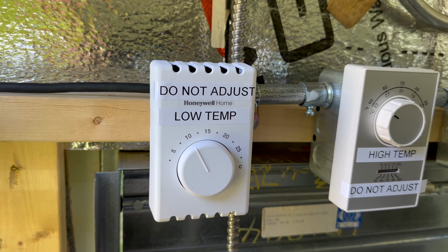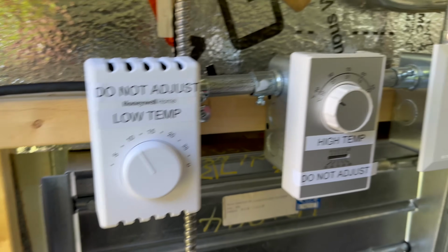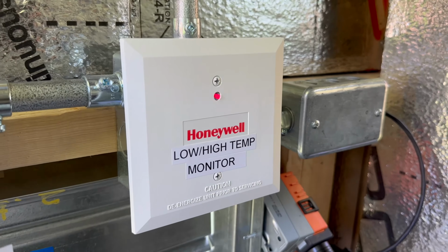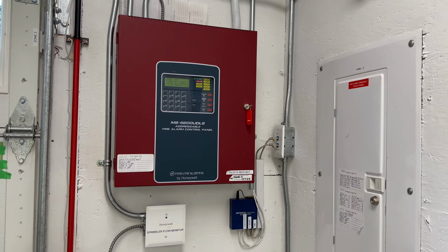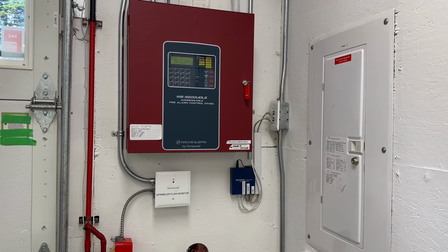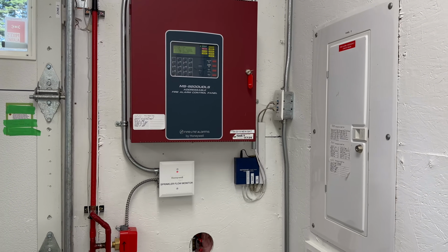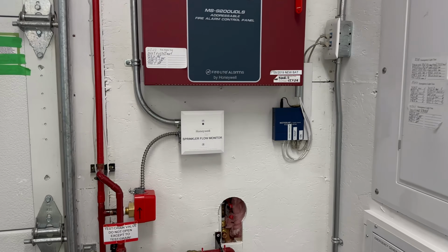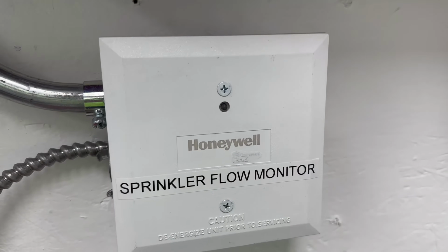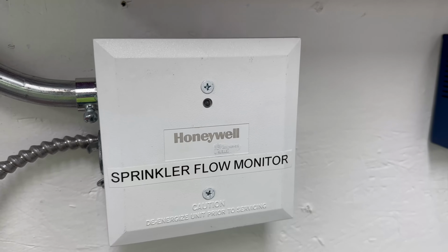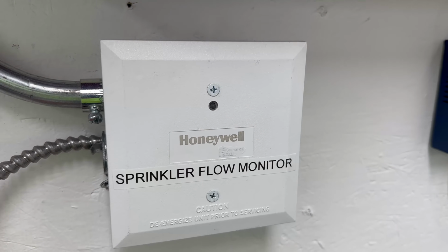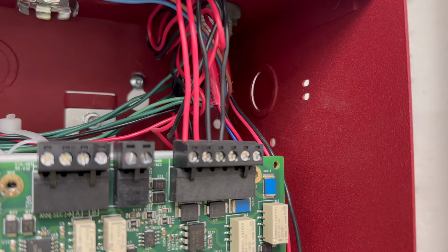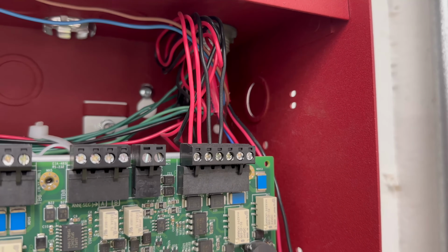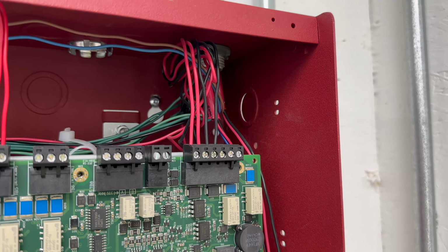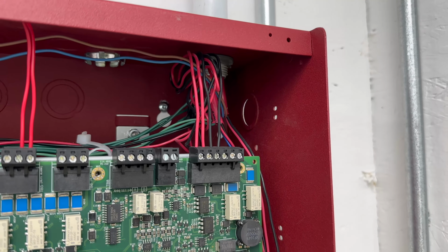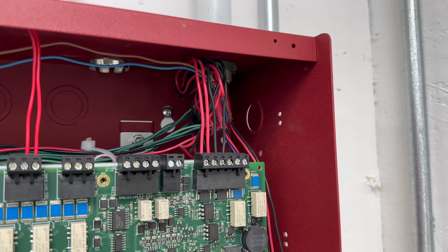However, these are tied into my commercial fire alarm system with this Honeywell addressable module. My fire alarm system that I have installed is an addressable fire alarm control panel with an addressable system, meaning that every single device uses what is known as an SLC, which stands for signaling line circuit. That SLC communication circuit comes out of here. It is a Class A loop, meaning it goes out on two different sides. So if it is severed in the middle, the other side can take over and you won't lose any of your devices.